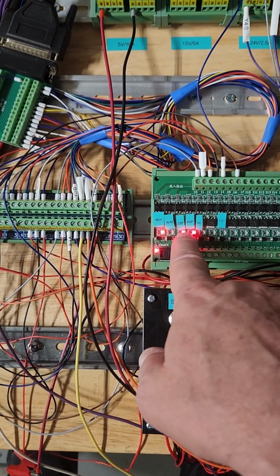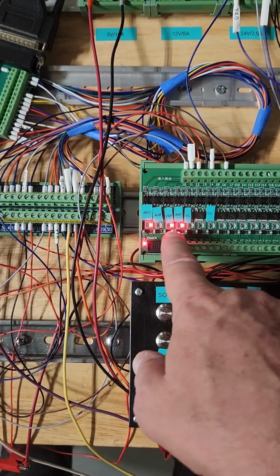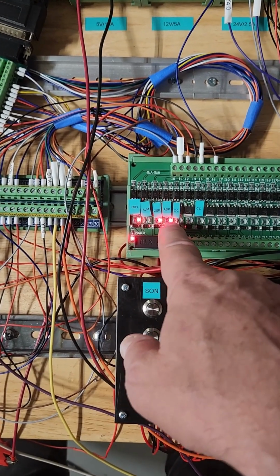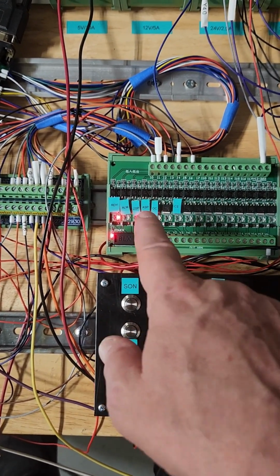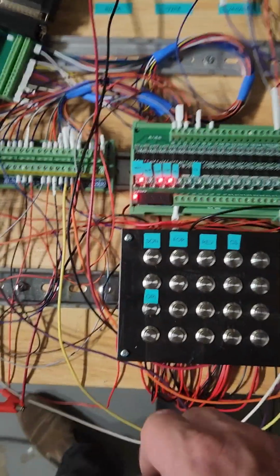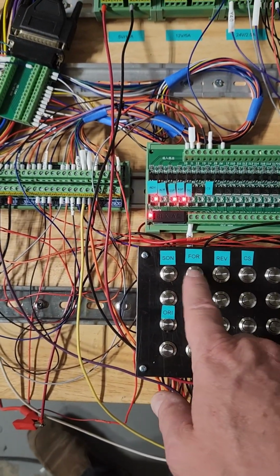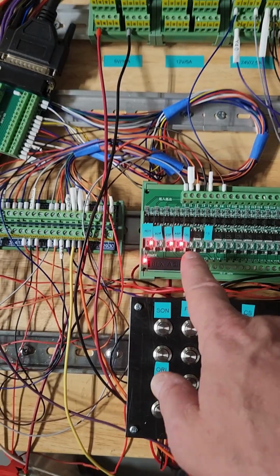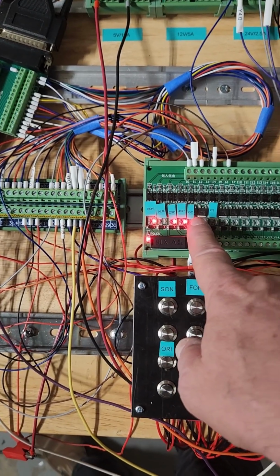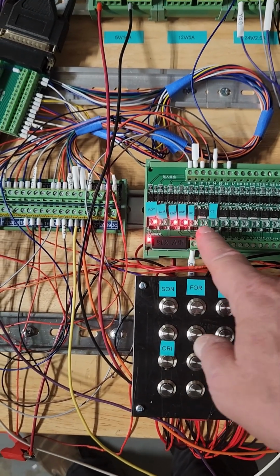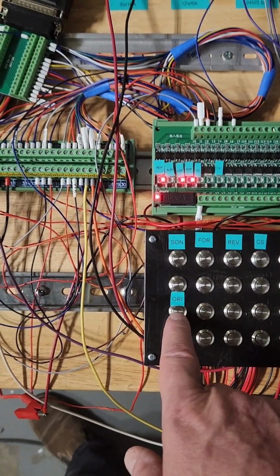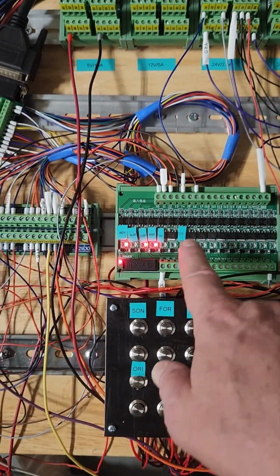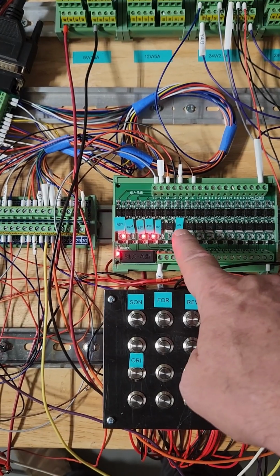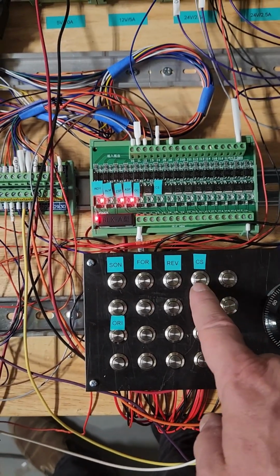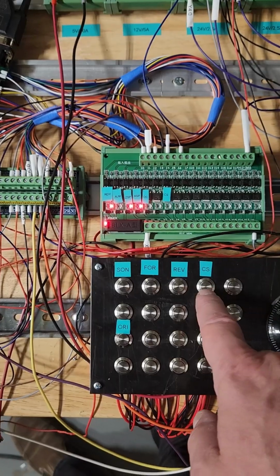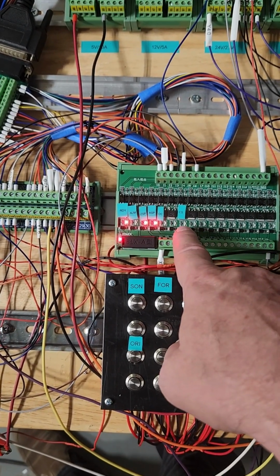It's at 0 speed - that ZSP means we are at zero speed. ASP, the next one, means we are at speed, at program speed, whatever that program speed is, whether running in voltage mode, speed mode, or positioning mode. Then OC is for orientation complete - this button triggers the spindle orientation. The next one is for switching to positioning mode, so that C-axis switch, you activate it from here and it feeds back there.